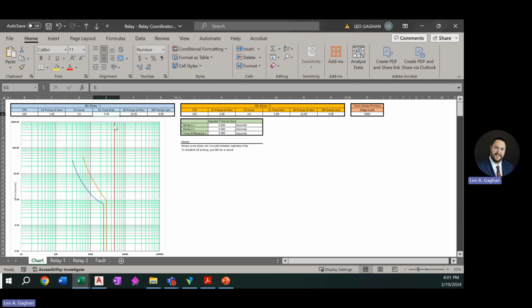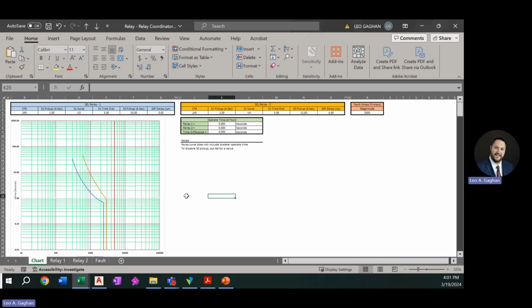We got the time dial. The time dial is intended to move the curve strictly up and down. So right now we're at 5. If I move it to 8, we'll see it moves up. If I want to move it to 2, we'll see it move down. We'll put it back to 5. The general consideration here. We've got the instantaneous pickup here.